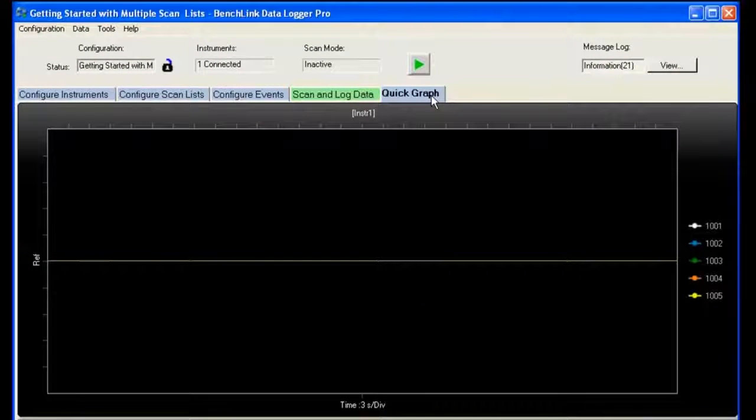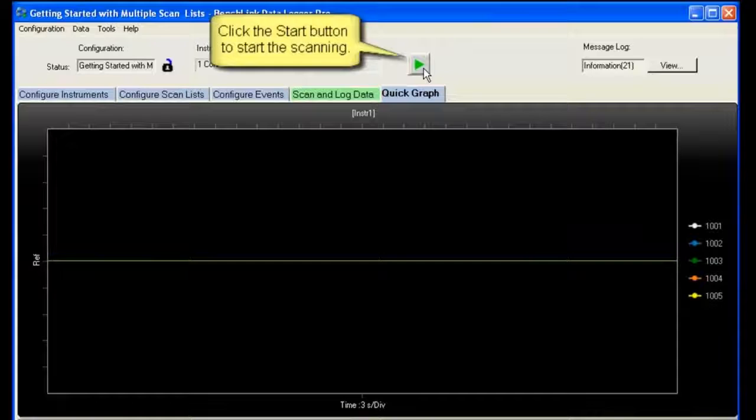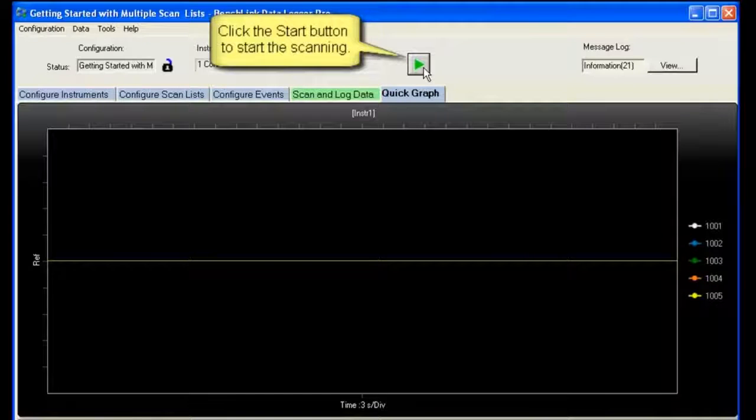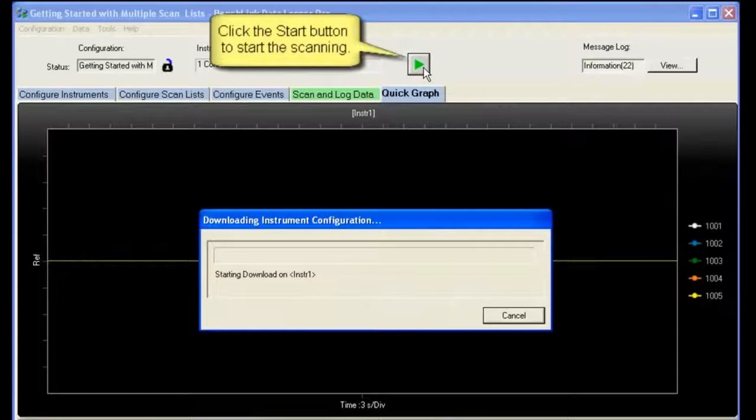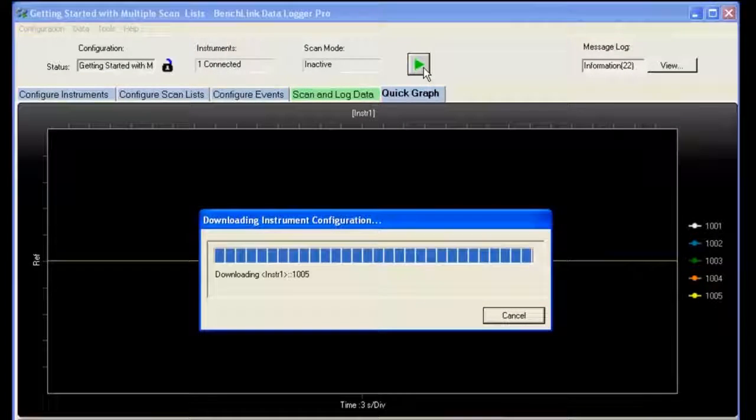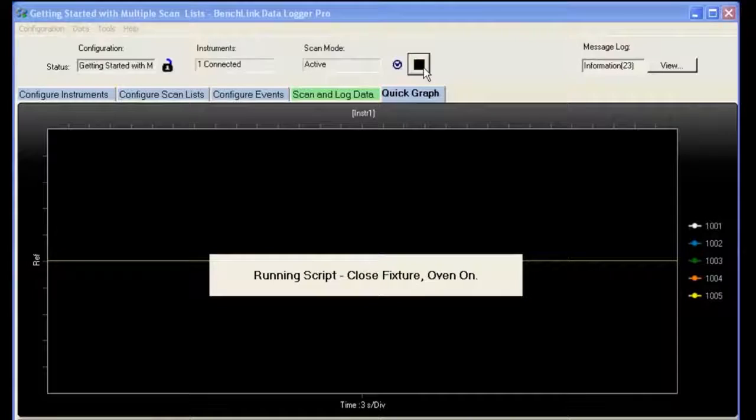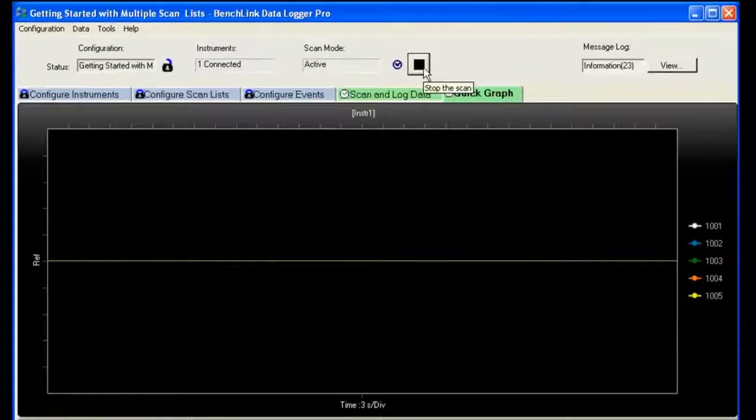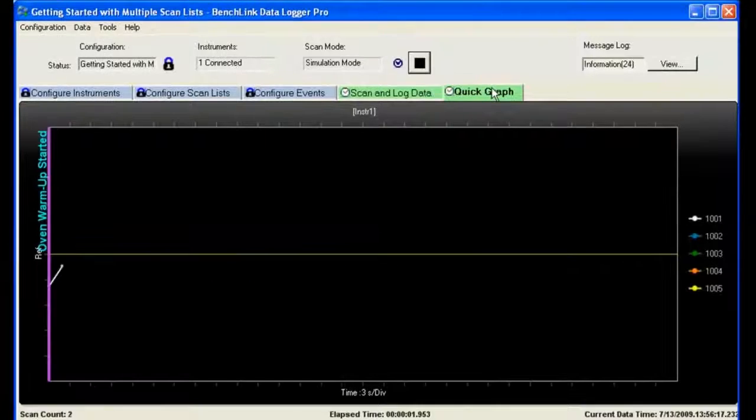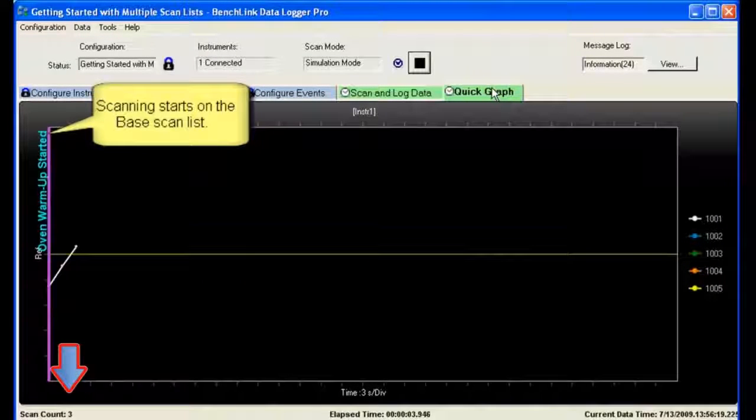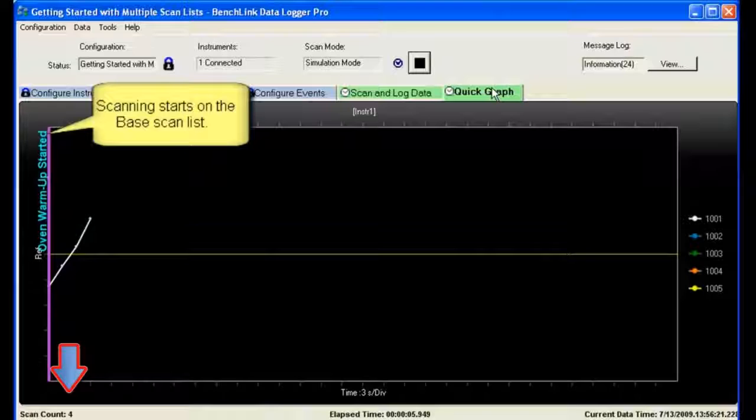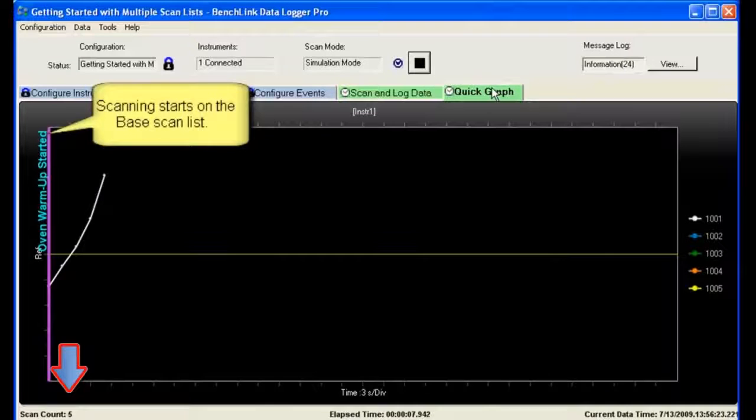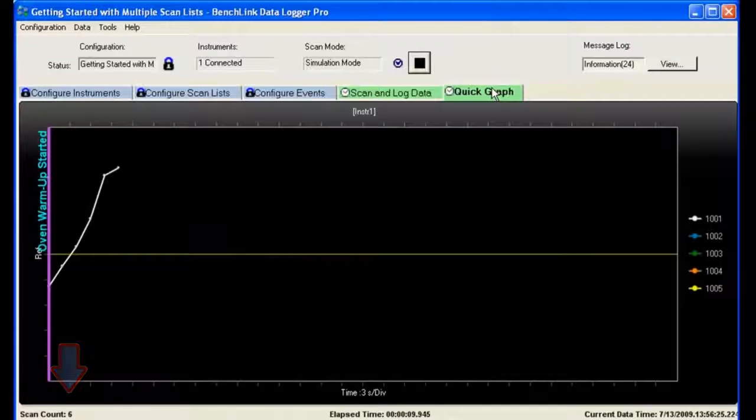So we're going to try and run it. I want to graph it first, and then I'm going to click the Start button. It'll download to the instruments and tell the instruments what to do and the sequence in which to do it. Then it starts running, and you'll see that once we run, you start seeing the temperature of the oven come up. You'll notice there's a countdown here. I'm up to three, four, five scans, and so forth.